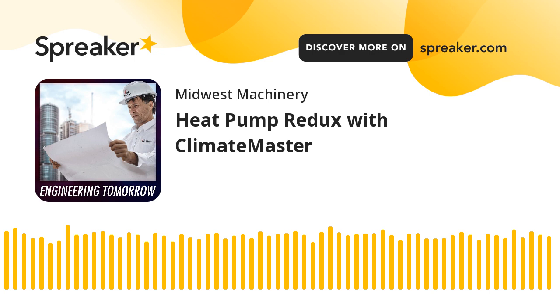Also with water source heat pumps, if we go back to that comment about simultaneously heating and cooling, if we think about some of those other systems that can simultaneously heat and cool, we have a 4-pipe VAV system. Now, they can heat and cool. However, they're going to require 4 pipes. The water source heat pump system on a traditional system would require 2 pipes, and we can also do it in a single pipe. So right there, we're cutting out labor and material to hang the pipe for the water loop.